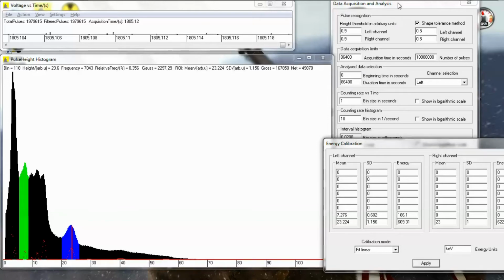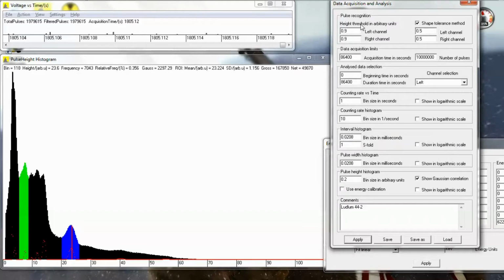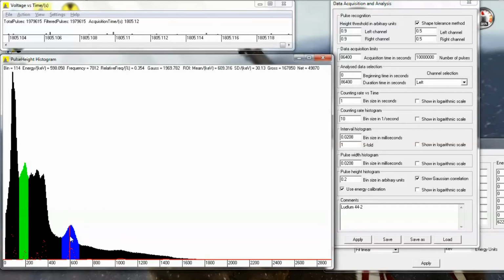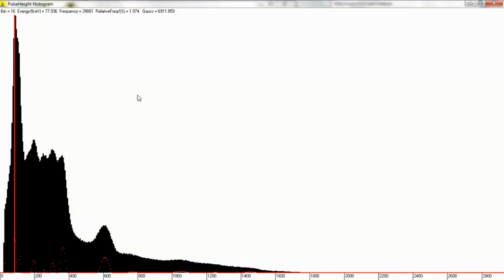And then we're going to come over here to the actual screen where we control everything, the data acquisition analysis screen. And we're going to use energy calibration. Boing. Now we're displayed in thousands of electron volts, so that's kiloelectron volts, otherwise known as keV, and counts going up. Alright, now that we have this together, let's delete these ROIs because we don't care about them anymore. I just wanted to show you what was here. Let's see if we can identify what we have here. We'll expand this to full.